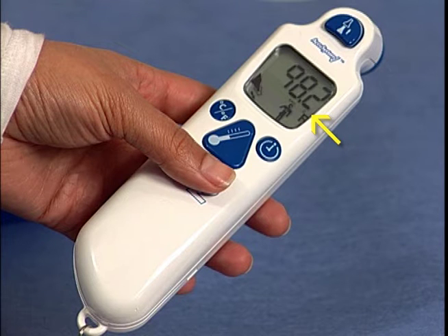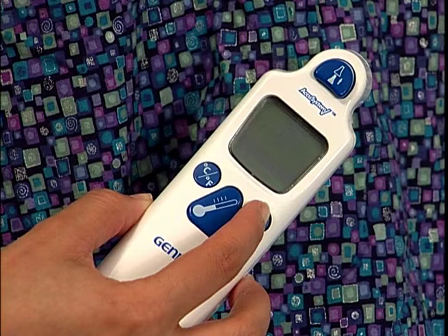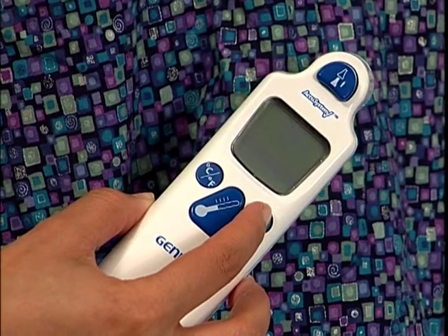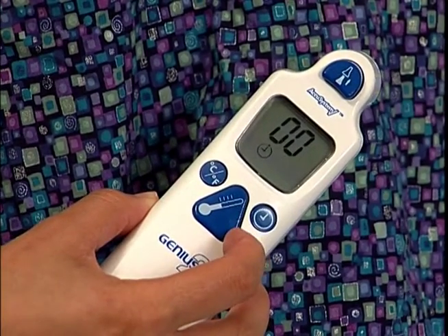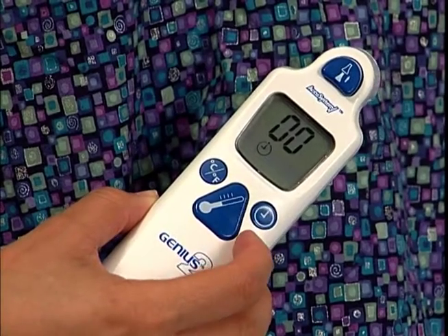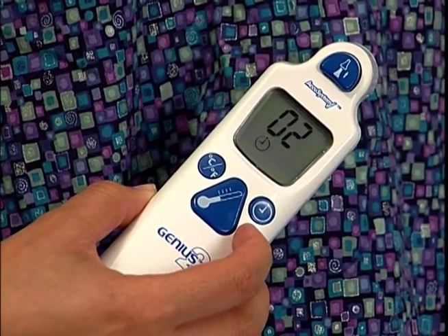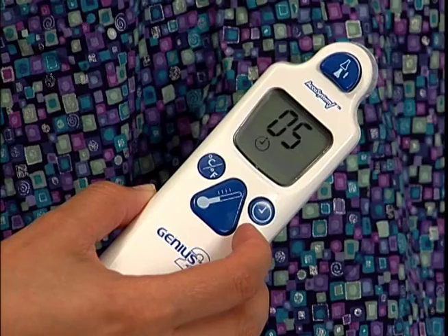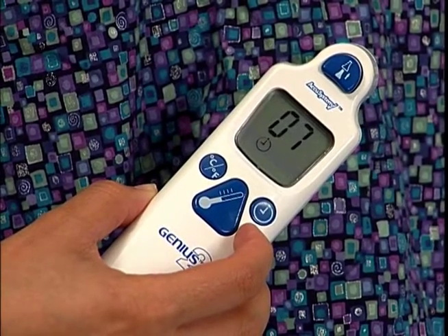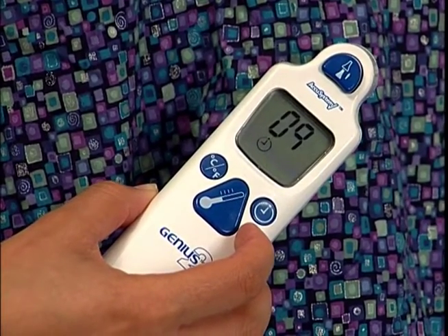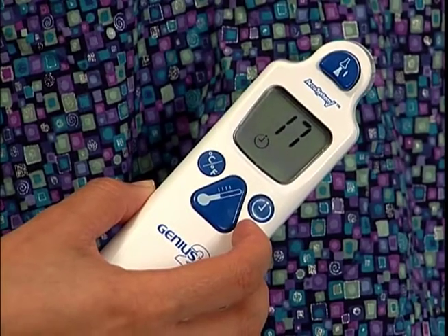easy temperature measurement process. The pulse timer button, located to the right of the large triangular scan button, displays a 60-second stop clock. To activate the pulse timer, ensure a probe cover is not loaded. Then press and hold the clock icon button. Press and release the pulse timer once to start the countdown. Beeps will sound in 15-second intervals.